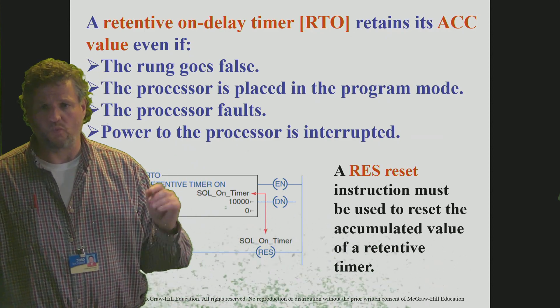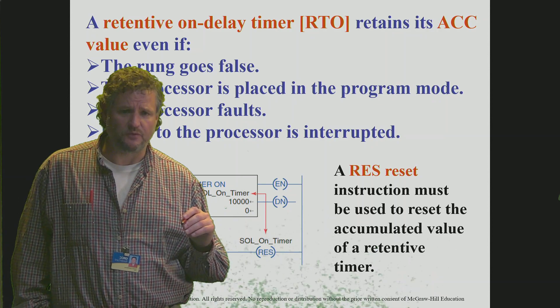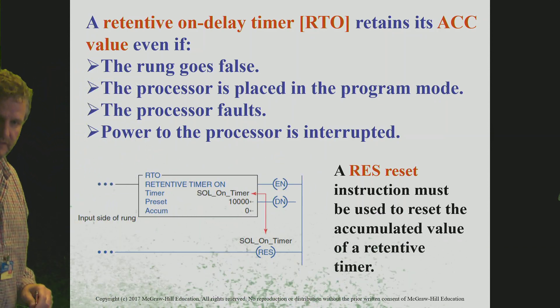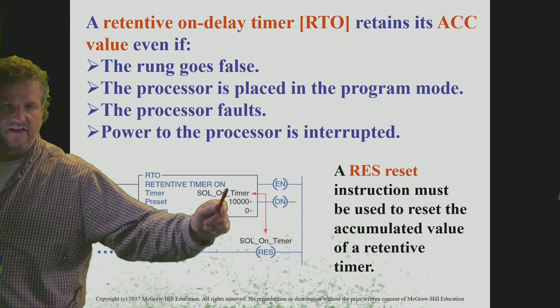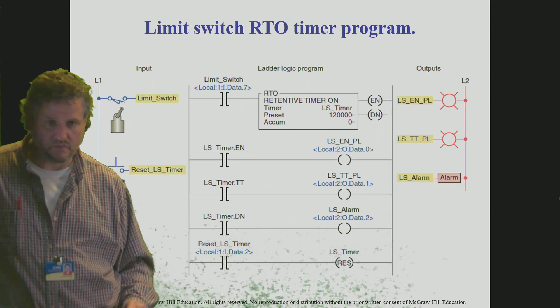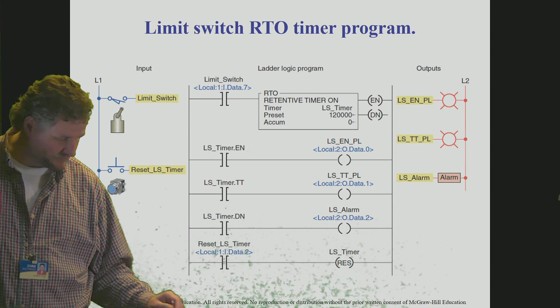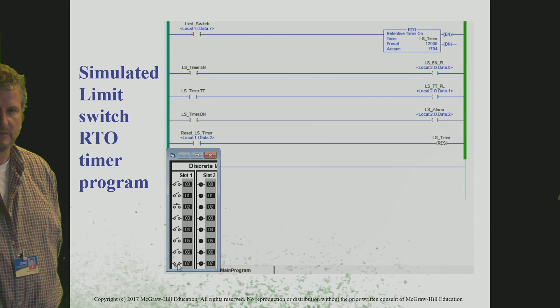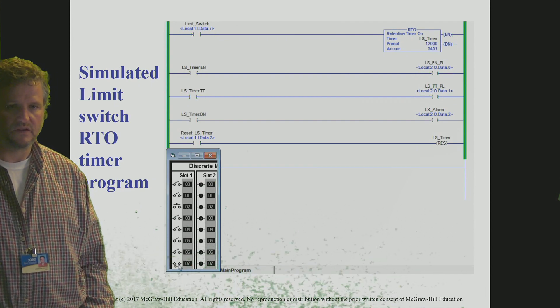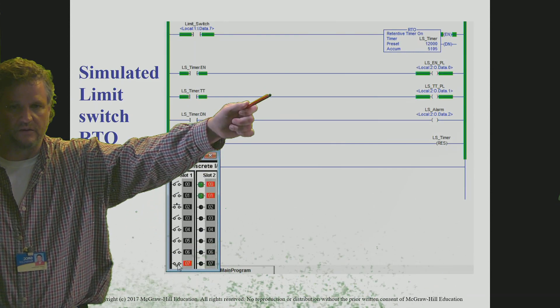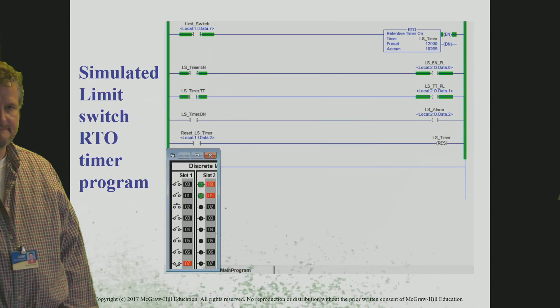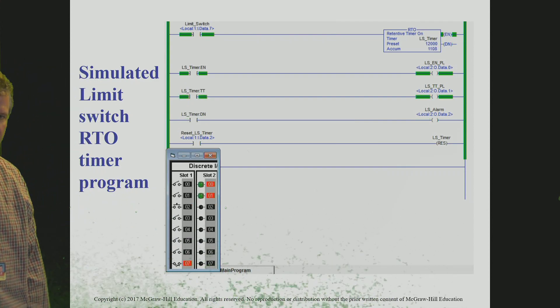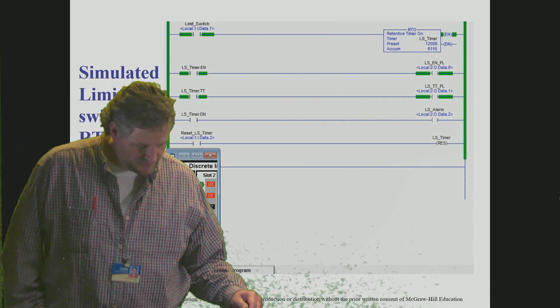The retentive timer works the same way as the timer-on, except it doesn't reset when the input goes off. We're able to retain the value in that timer until we hit a reset. That reset has to be addressed with the same address as your timer to reset it. As you can see in the example, it is timing, then stops timing when you take away the input, then resets when you trigger the reset — going back to zero. The done bit is on as expected, and after reset it starts timing again immediately.